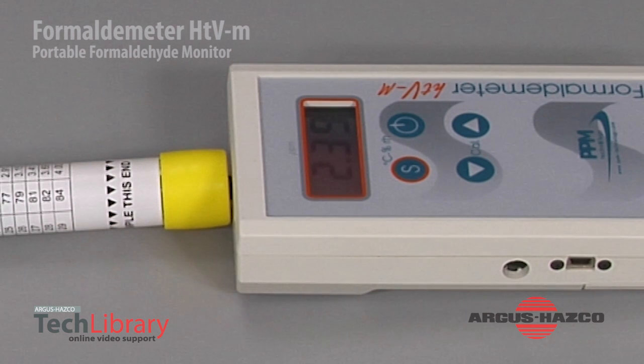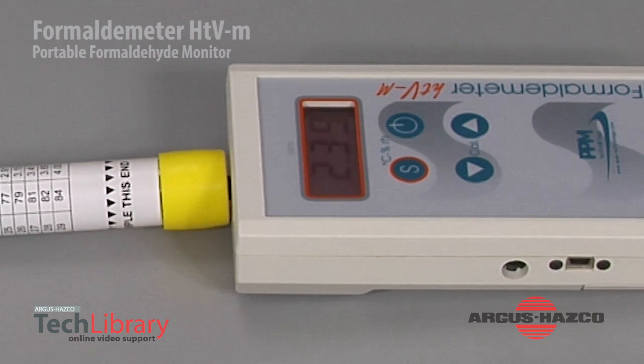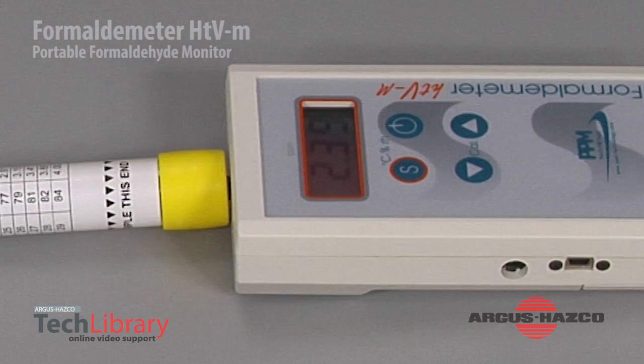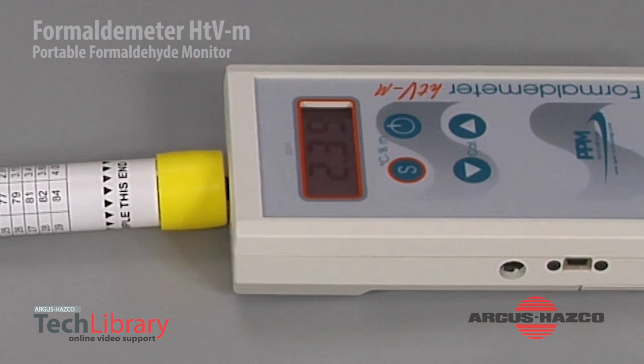Once it stabilizes, you'll see 2.00 staying constant on the screen. At that point, we make the adjustments to equal what's on the calibration standard. In this case, we're calibrating it to 2.49 ppm. Again, it's a relative response factor that we're incorporating into the instrument.